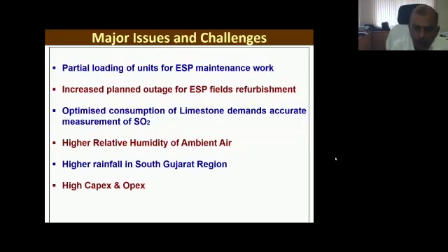With the measurement of SOx, we try to optimize limestone consumption, but because of limestone quality and reactivity, it is in the range of 7-10%, affecting boiler performance. In South Gujarat, there is an issue of high relative humidity of ambient air and high rainfall, particularly during monsoon, causing feeding issues that always affect environmental performance like SOx.